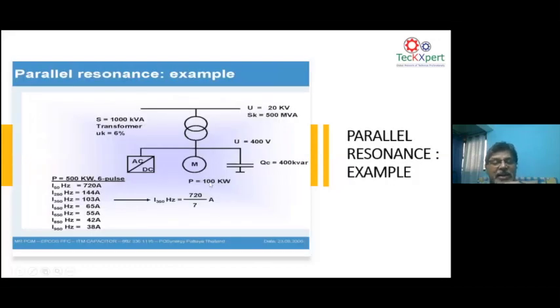There is a seventh harmonic current generated by a variable frequency drive. If you remember the Fourier transformation I was telling you about, the magnitude of every harmonic will be a division of your fundamental current. The fifth harmonic current will be 720 divided by 5, and the seventh harmonic will be 720 divided by 7. So the seventh harmonic current in a normal situation will be around 100 amps.